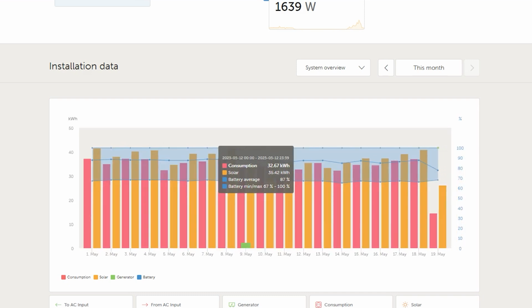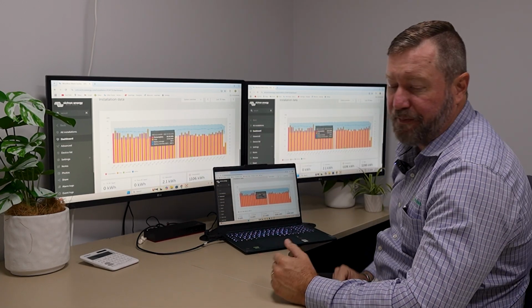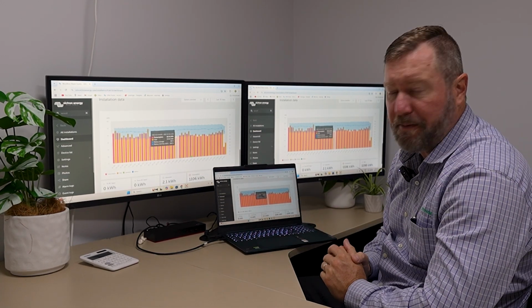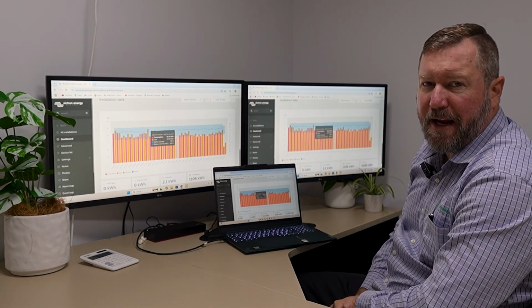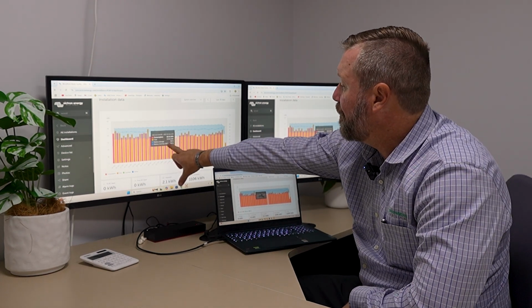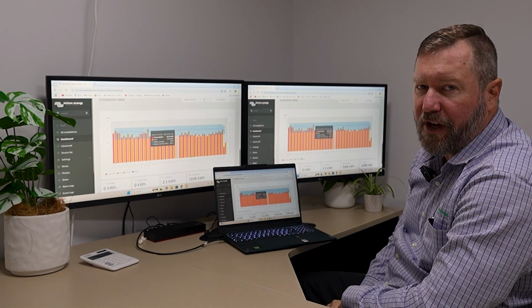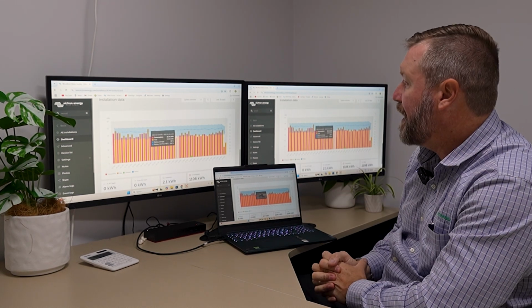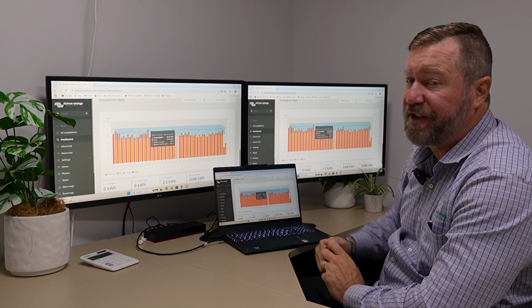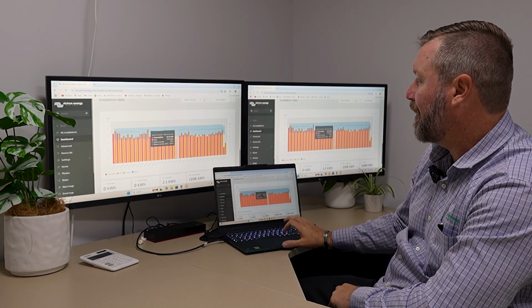This blue band at the top is our battery state of charge - hovering over it, we see the battery going to a minimum of 68% each day and a maximum of 100%. The brief required 2 days autonomy; we'd get 3 days autonomy out of this system with not much sun, because we're only using 30% of its capacity each day, and we could sustain the energy needs required for this site over a number of days.